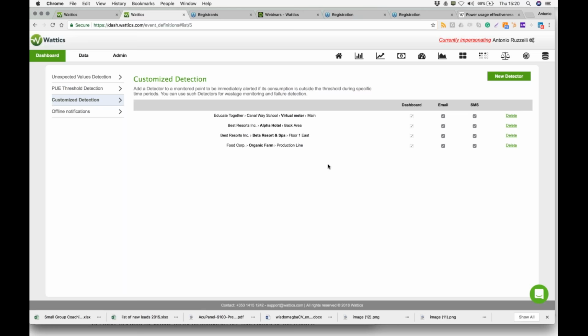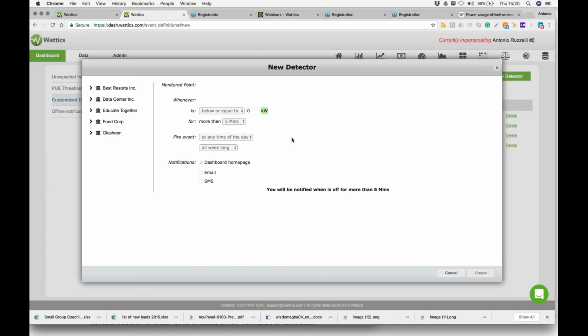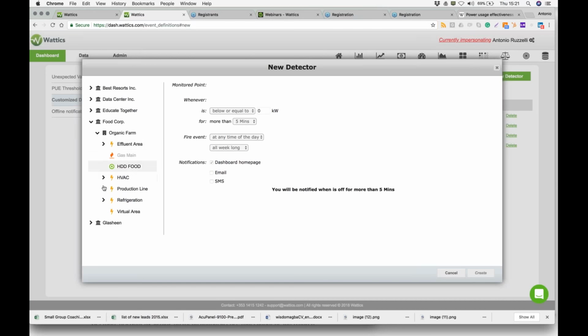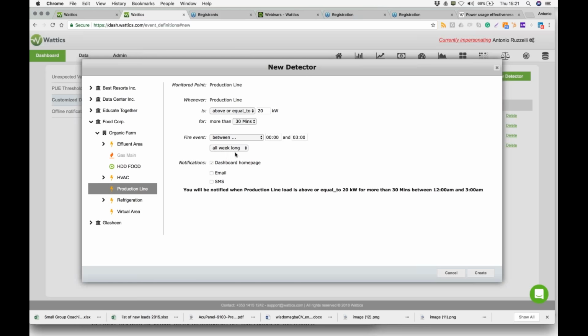The final one is the customized detection. At the moment, it's only a detection on kilowatts, and we thought that was quite a limitation, since the notification was only on active power. You would select a meter, a production line, and be notified if the kilowatt-hour is above, for example, 20 kilowatts for more than 30 minutes at any time of day, or between midnight and 3 a.m. You could pick and choose the days of the week you'd like the system to run, and be notified by email or SMS. There's a description here of how the customized detection works, above or below a certain threshold.